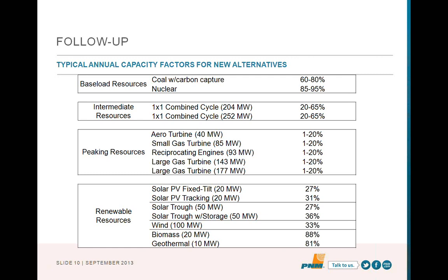After it's built out thousands, it looks at the net present value of all thousands of those and sorts it. So when it sorts it, you'll come up with the least cost. And depending on conditions, what was more valuable to me at that time? Was it capacity? Was it, I need more cheap energy? It'll balance those things in the calculation of cost, and by sorting it, it gives you a portfolio that's the most valuable mix of capacity and energy. So, long version of the answer to your question, which was yes.